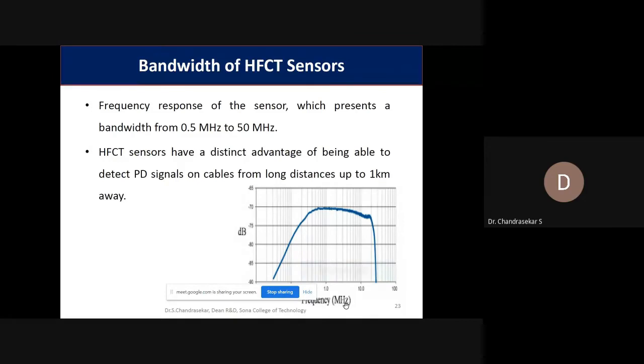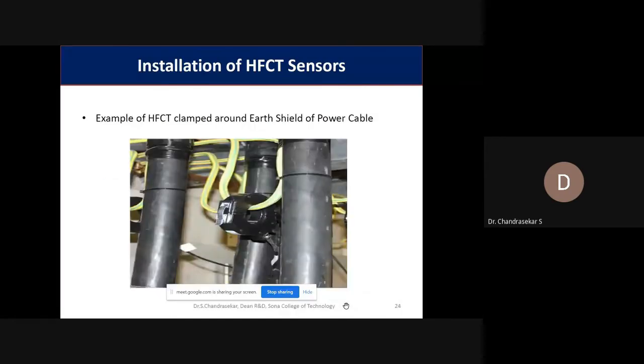The major advantage of these HFCT sensors is that they can measure the PD signal or any high frequency transient signals occurring in cables at a distance of 1 kilometer. Okay, so up to 1 kilometer also, these types of sensors can easily measure what is happening in the transformer or cable. And this is a typical photograph which shows the HFCT sensor connected in a power cable.